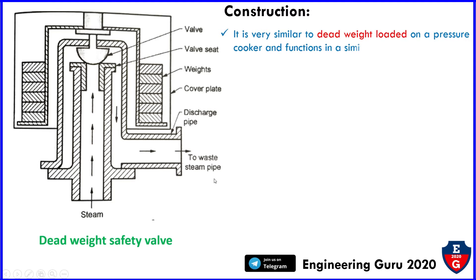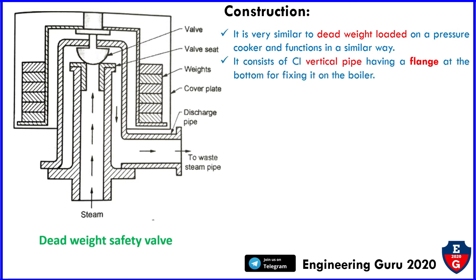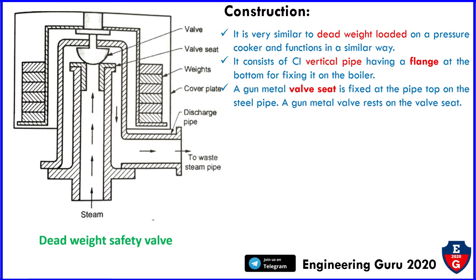Starting with construction — it is very similar to a dead weight loaded on a pressure cooker and functions in a similar way. It consists of a cast vertical pipe having a flange at the bottom for fixing it on the boiler. A gun metal valve seat is fixed at the top of the pipe. On the steel pipe, a gun metal valve rests on the valve seat. In this figure we can see the valve and the valve seat. The valve is fastened to the weight carrier.